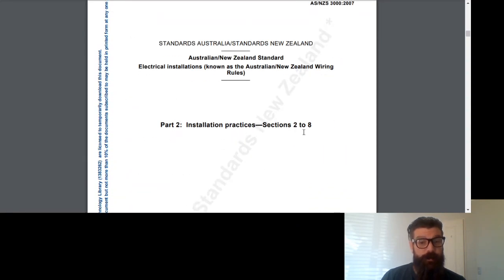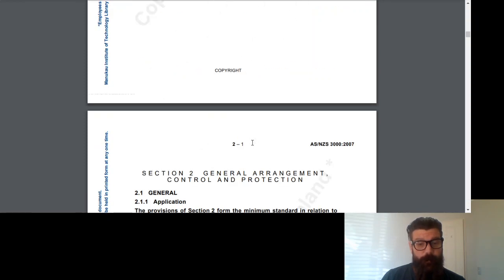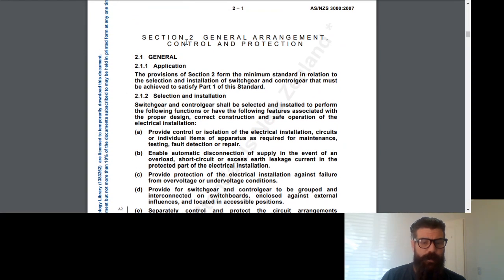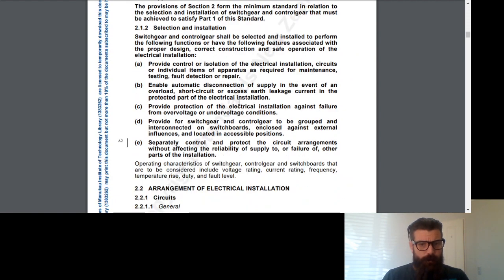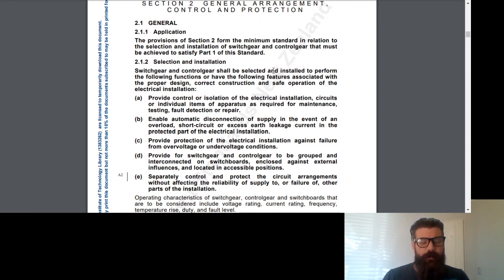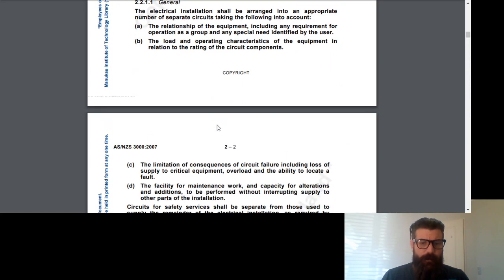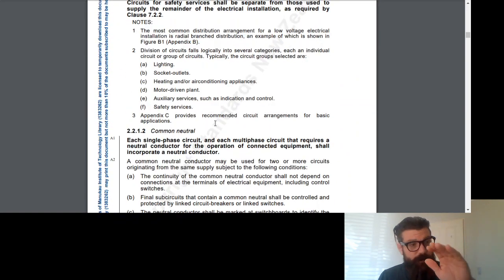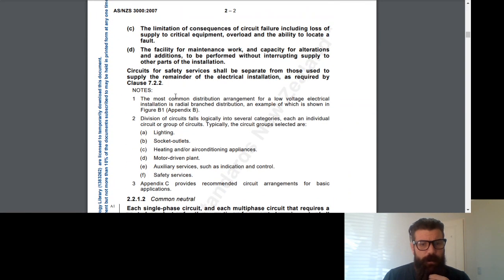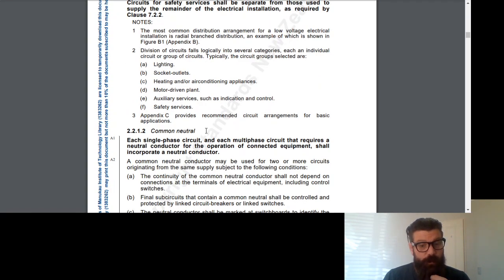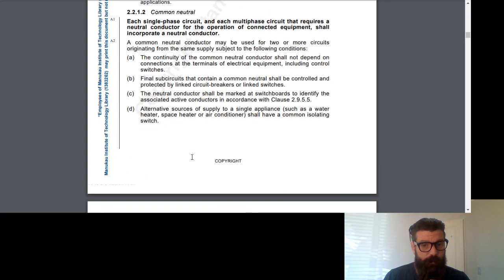So we get to part 2, installation practices. In section 2, which is the first section in part 2, tells us about the selection and installation of switchgear and control gear. So that would be all the stuff that's inside a switchboard. When we say switchgear and control gear, we mean circuit breakers, main switches, RCDs, that kind of stuff. And then obviously that section has various subsections. So it's talking about here, what have we got? 2.2.1.2 common neutral. And it tells us the rules for common neutrals.